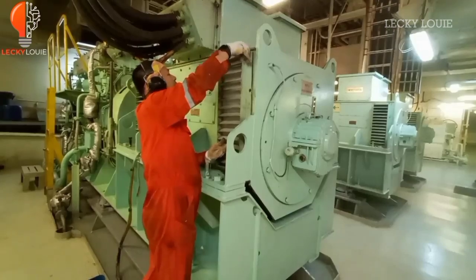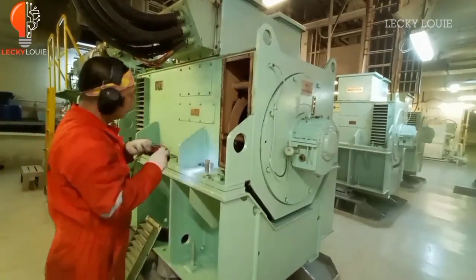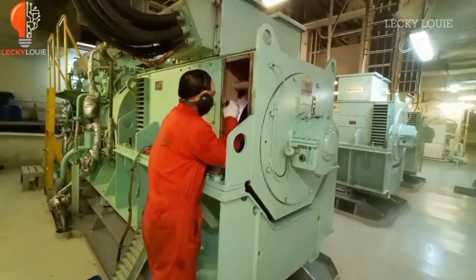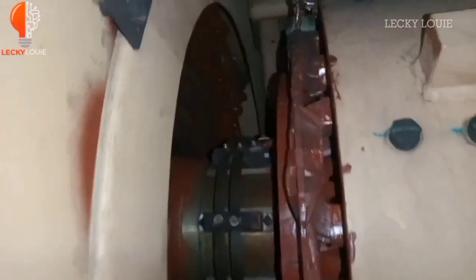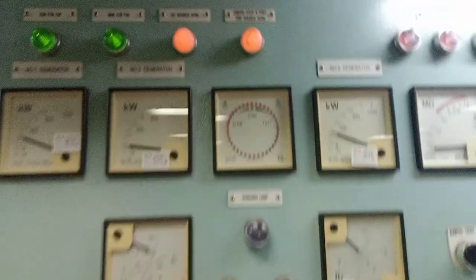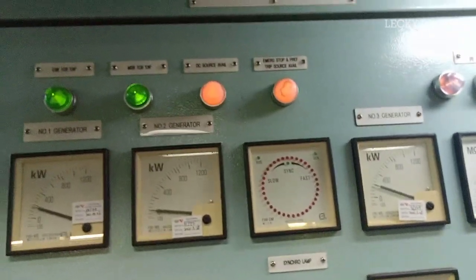To counter this kind of problem, a reverse power protection is installed in the switchboard to automatically release or trip the main circuit breaker to prevent the generator motoring if reverse power occurs. Since this is one safety protection of the main switchboard, it requires routine testing to make sure that the reverse power protection is still working.